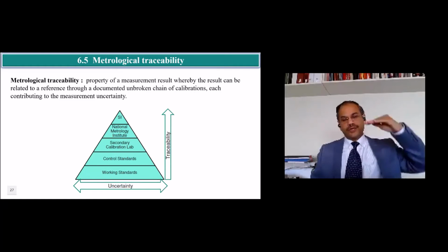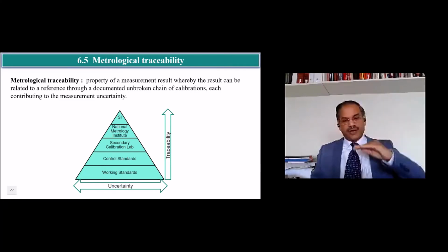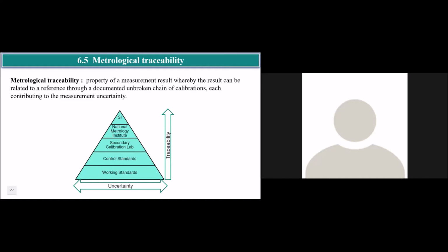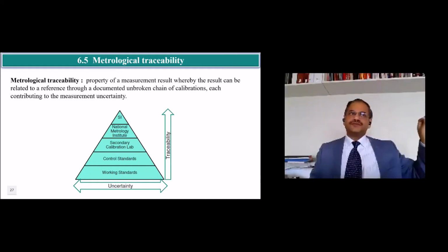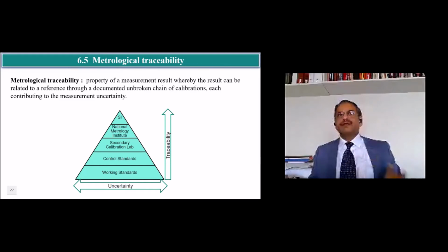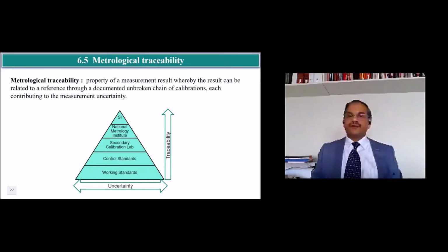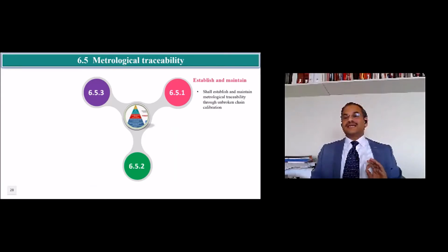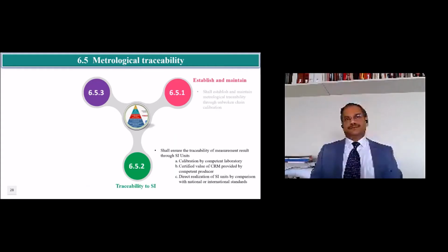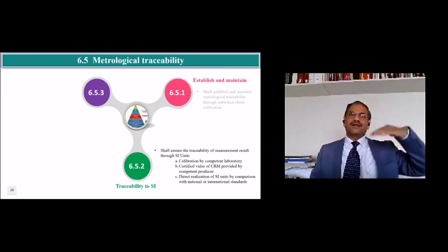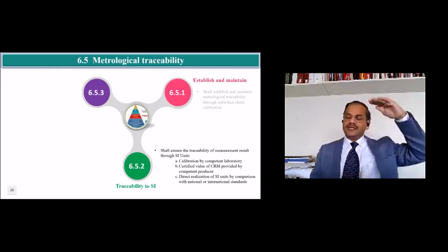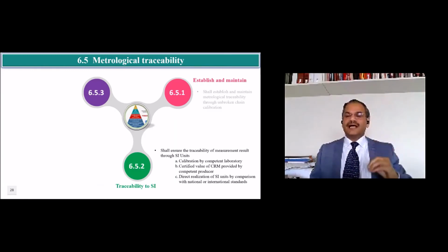So as you go up, your uncertainty goes down. Suppose you have a weight box at NPL India, the uncertainty is very, very low, whereas when you come to your lab, the uncertainty may be very high. So these are metrological traceability. What are the requirements? You have to establish and maintain metrological traceability for all your calibrations. Indirectly, for a result, it shall be traceable to the SI unit. How? You can go to a calibration lab, to NPL, to NIST. An unbroken documented chain of traceability has to be maintained.